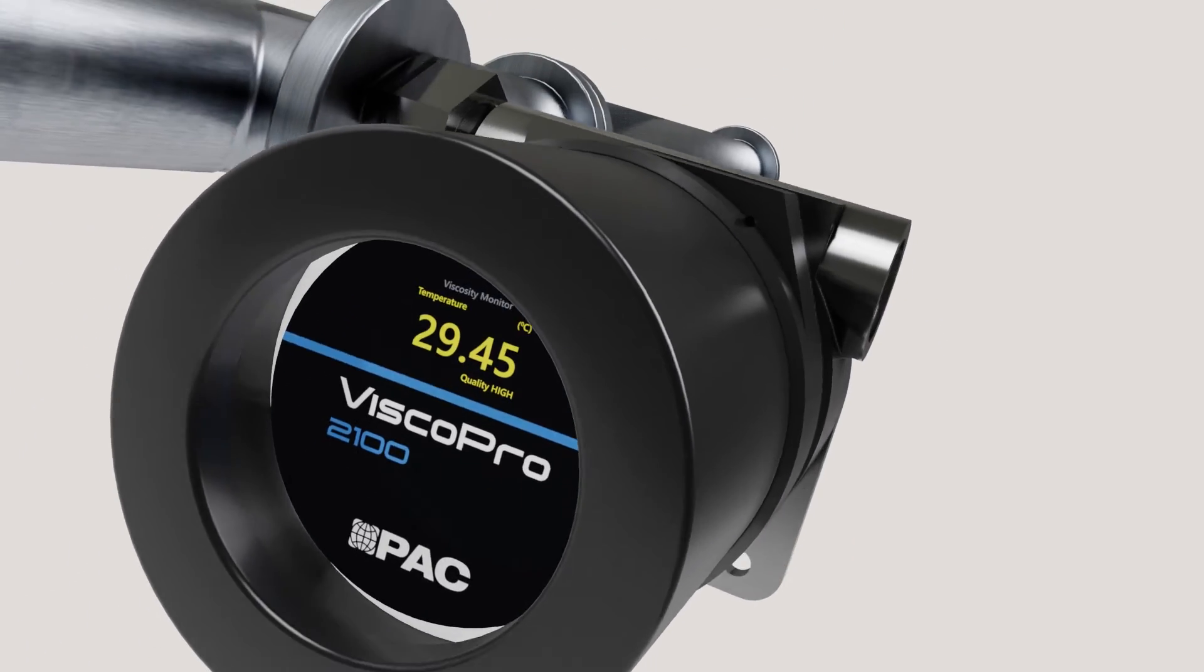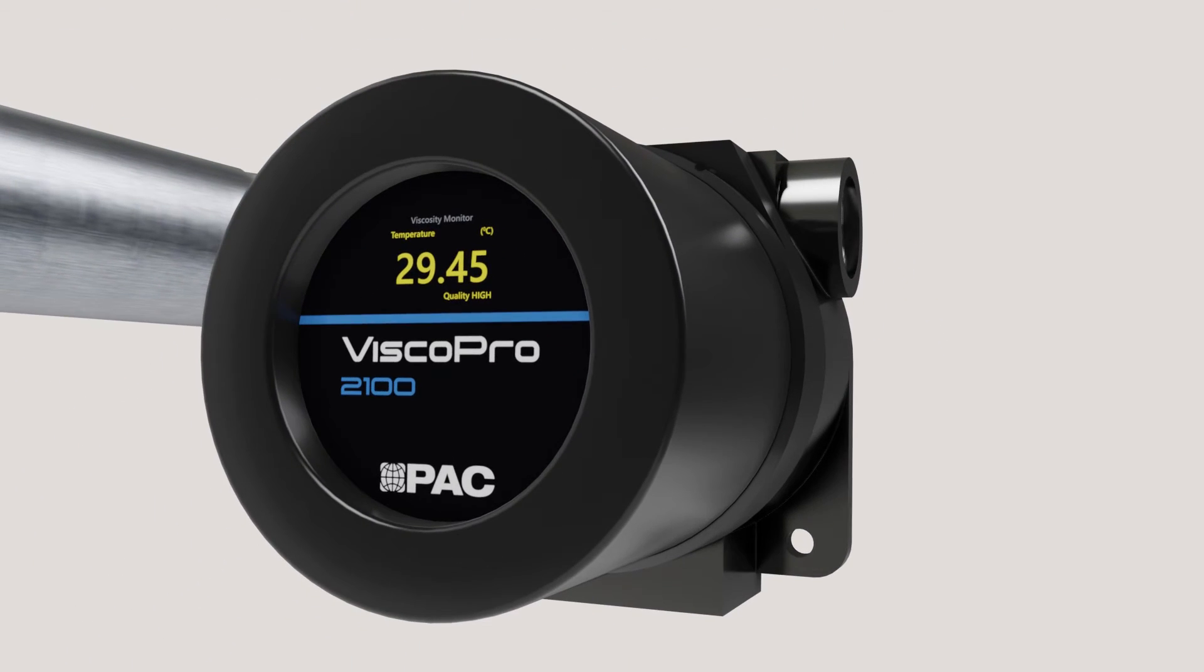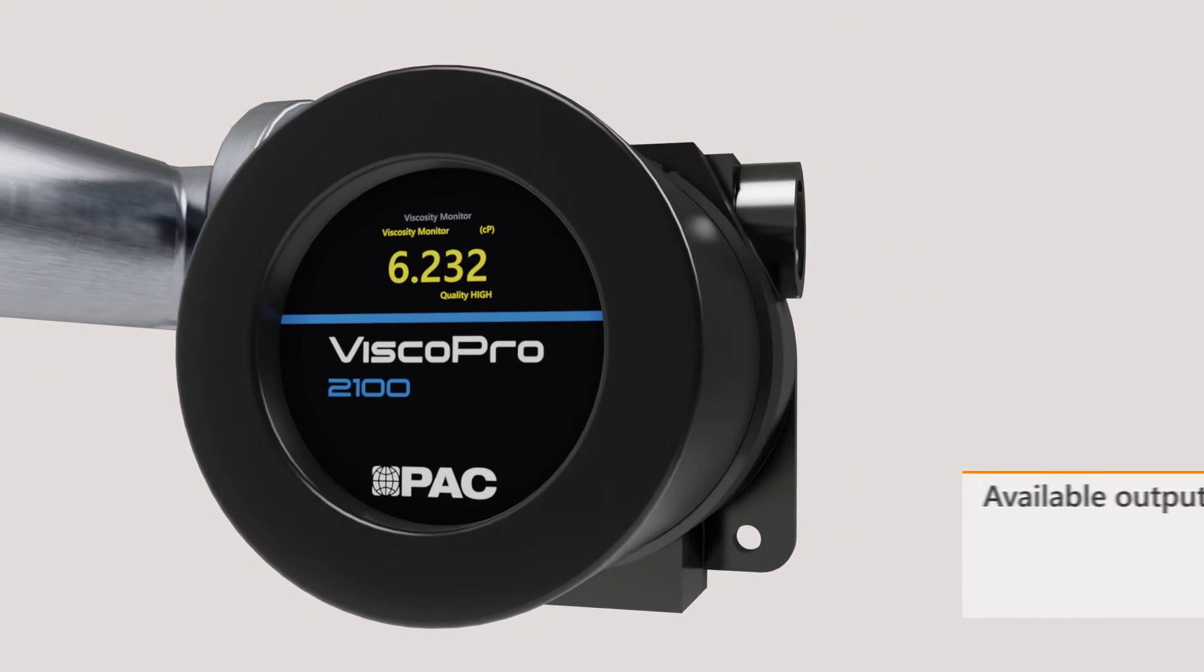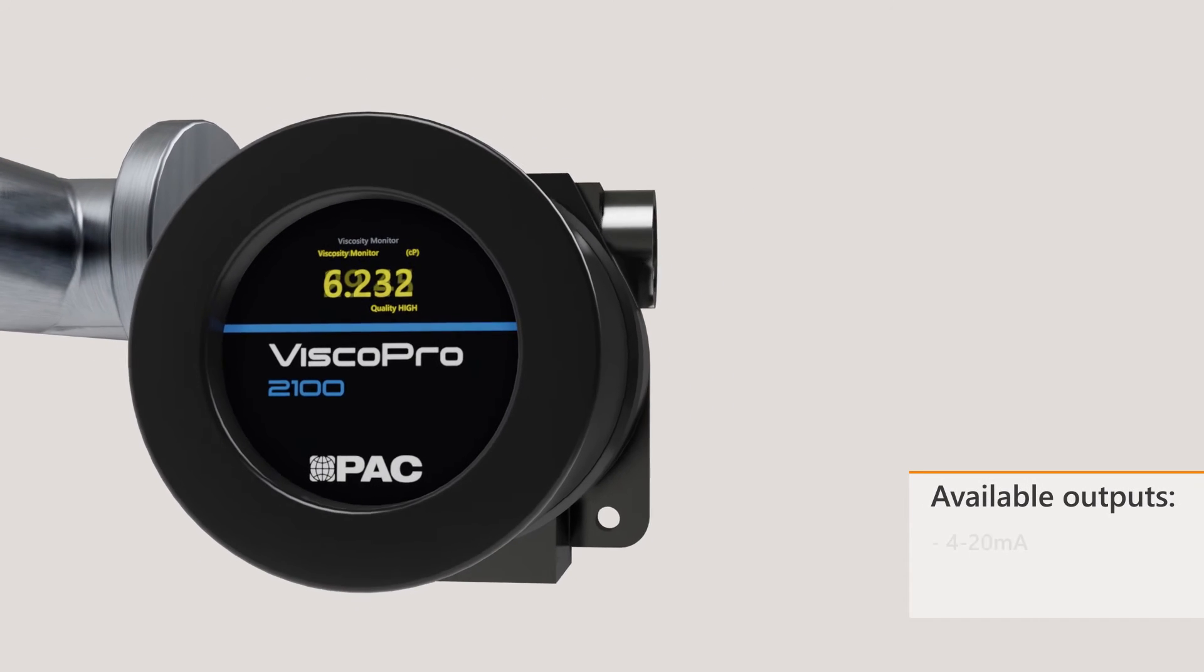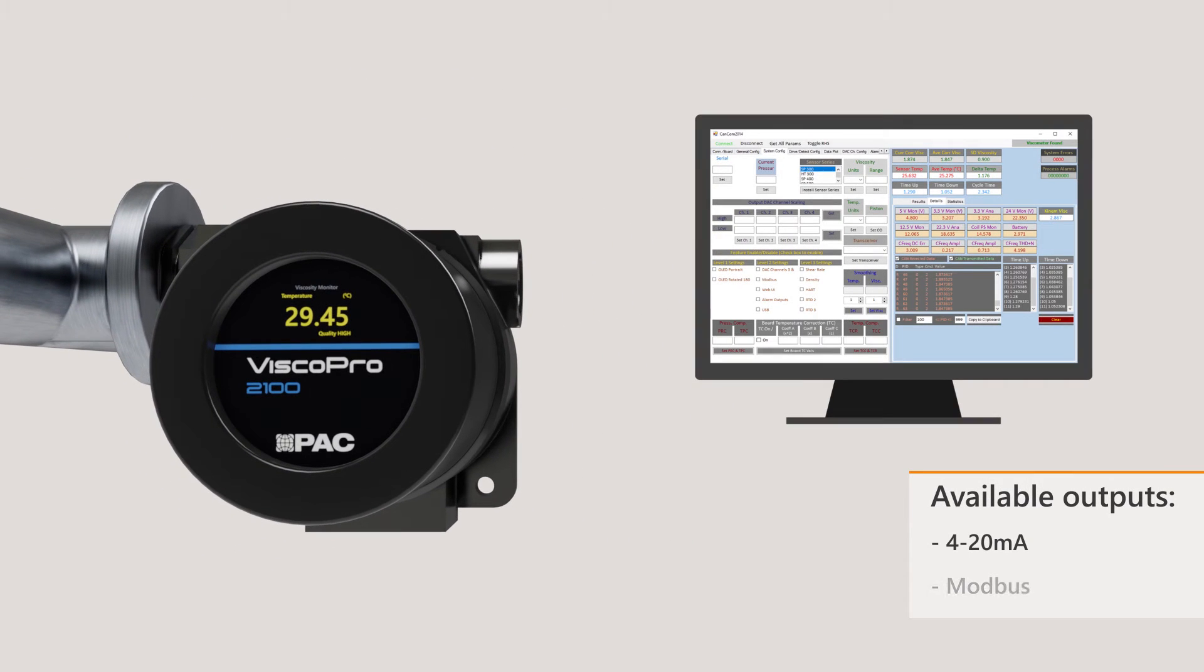Measured data is displayed directly on the analyzer. Outputs are available in 4 to 20 milliamps and Modbus to allow customers access to information where they need it most.